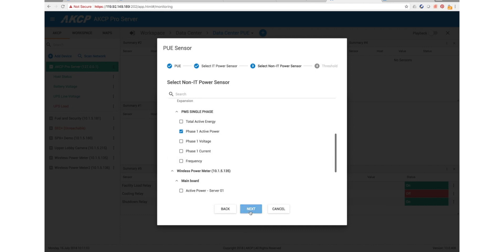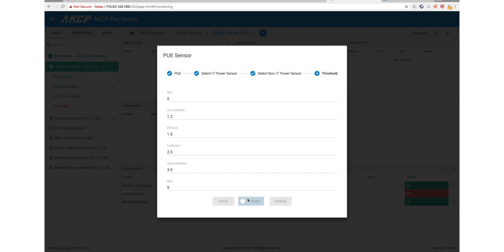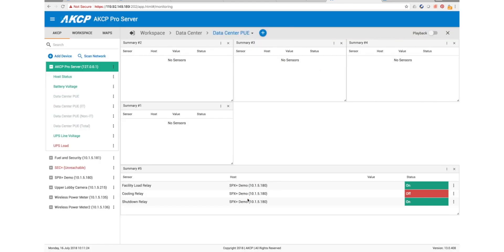Then next, and then this is where we can set our PUE efficiencies. If we're 1.2 to 1.5 we are in a very efficient range. Above 1.5 we're efficient. Once you get up to 2.5 we're inefficient. And then hit finish. That's it. Now this will automatically be set up and added here.